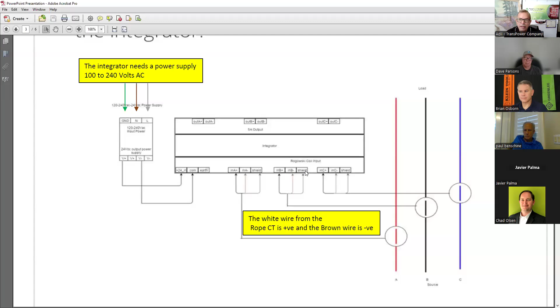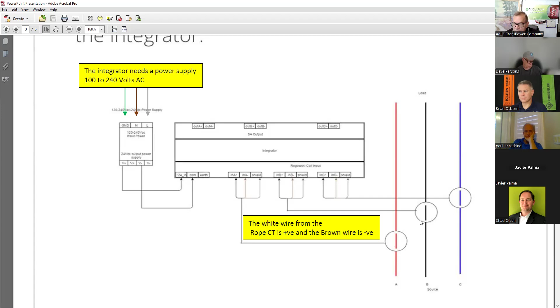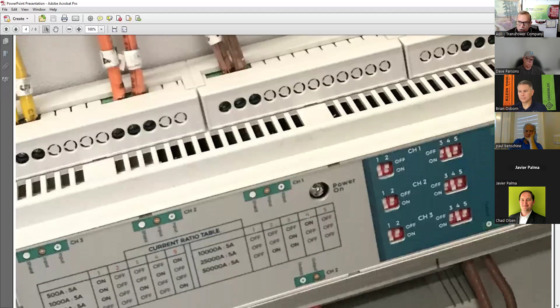And the distributor, wherever you're buying the equipment, they now supply this bundled and they're quoting a price. Sometimes the contractor says, no, I have CTs, I don't want you to supply it. And now you have a problem, because now you have another variation that they might do something and you don't know what happened. But these Rogowski coils, when you install it, because they're rated to go all the way up to 50,000 amps, you have dip switches on the integrator kit.